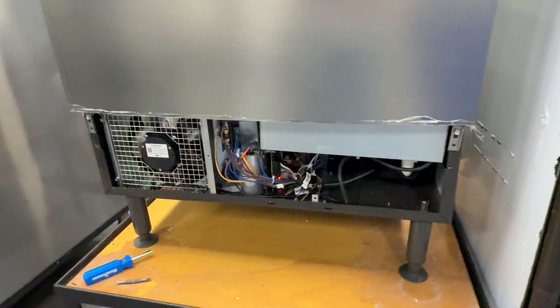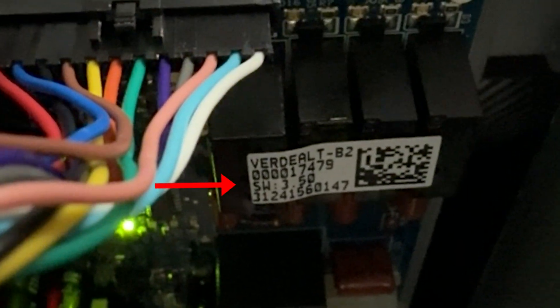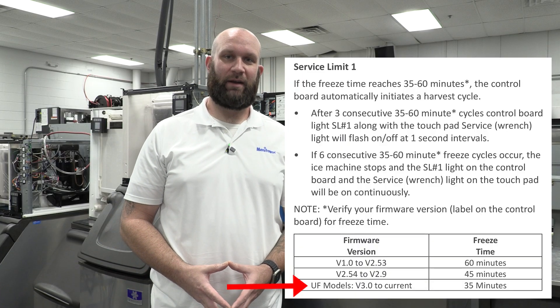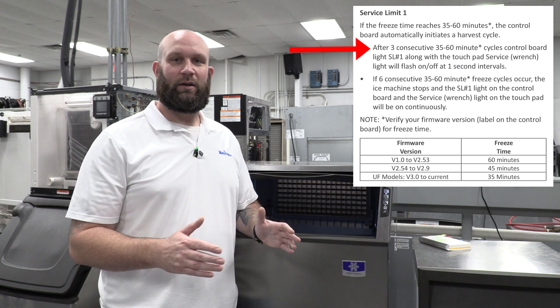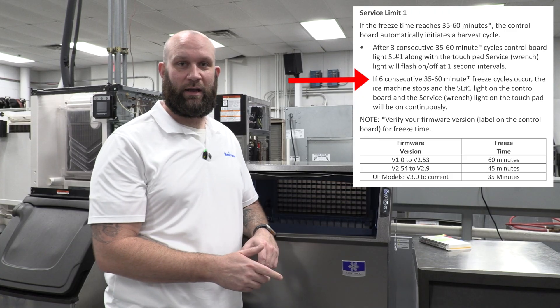I've gone ahead and removed the louvered panel as well as the control box cover. If you take a look at the sticker on the relays, you'll see we're currently running software version 3.2. For our machine running version 3.2, we're going to have a maximum freeze time of 35 minutes. We'll get the flashing wrench light if we experience that three times consecutively, and if we experience it six times consecutively, the machine will lock out with the solid wrench light like we saw in the beginning.